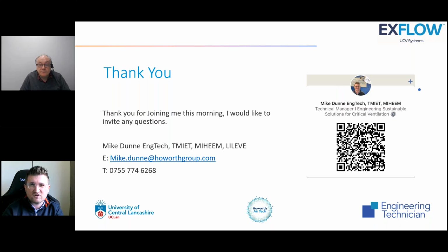I'm guessing we're talking about the air handling unit there. So it's acceptable to have a single fan inside the air handling unit if a replacement fan is wired and local to the air handling unit and can be replaced in something like 30 minutes, or something along those lines as it's worded in HTM. As long as you've got a robust method of replacing that fan, the HTM says that's acceptable. I'm not sure of the actual section off the top of my head.